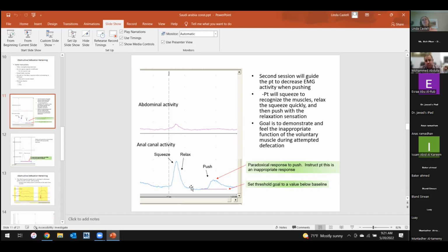Then I put my catheter in so all 23 sensors are in the rectum, and for that second reference line, I do a rectal baseline measurement. I pull out my catheter, and if I see a lot of variability, some dropped below 0, some are 20, some are 30, they're not all at 0, then I use my atmospheric baseline for my measurement, and I delete my rectal baseline measurement.